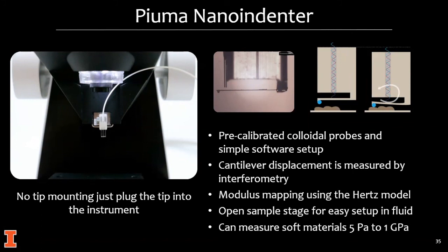But for the Petri dish setup, what I like to do is have enough fluid just above the sample that you can get the tip into the fluid, that it breaks the surface tension, and you can actually get a stable optical signal. And once that happens, then that's enough fluid. Other than that, it's just excess. You can start with more to do this optical signal calibration, and then you can just take some out as you're doing the measurement, so you can change it over time.